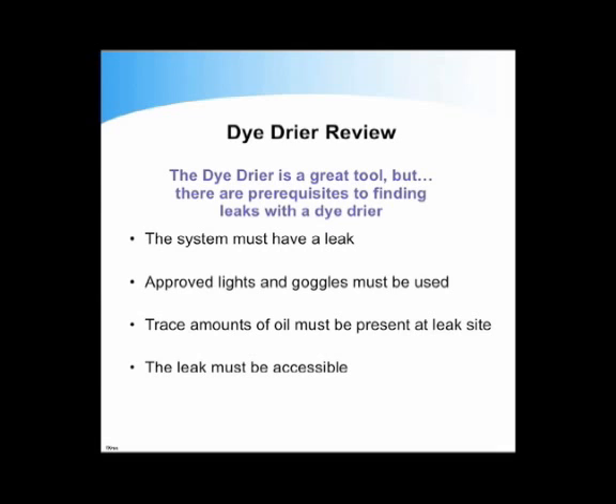Dye dryer review. We assume that most of these are known, but we must be sure. The dye is carried in the oil, so that's why oil must leak to get the glow. 99.9%, almost all leaks are repairable. Inaccessible leaks would be any tubing within the foam, such as the heat loop or heat exchanger. There are no joints on tubes in the foam. Where are most leaks found? 99.9% are at joints or on exposed tubing that got damaged.